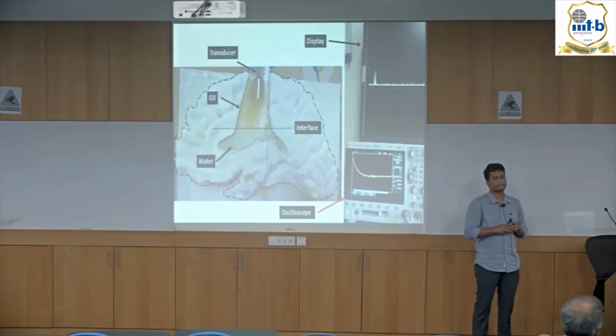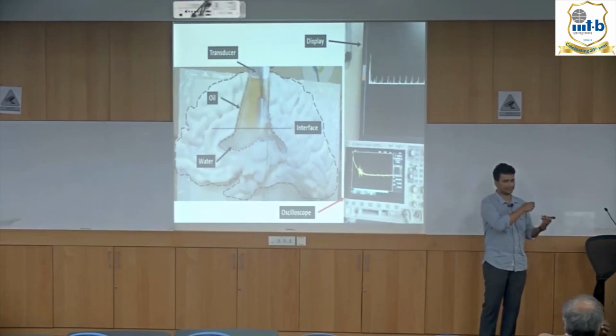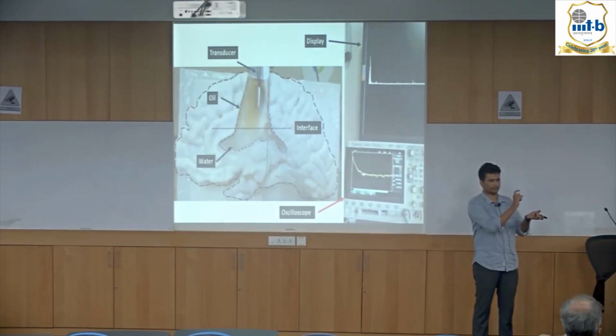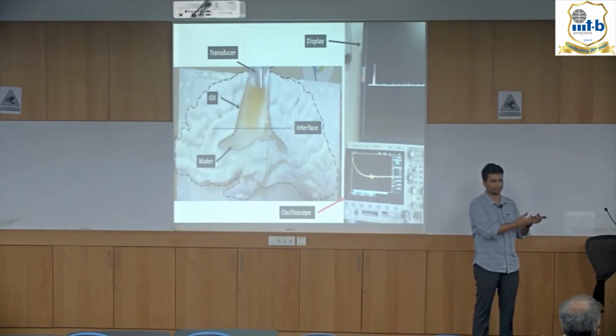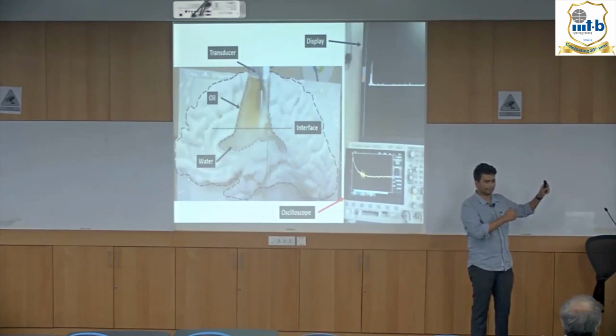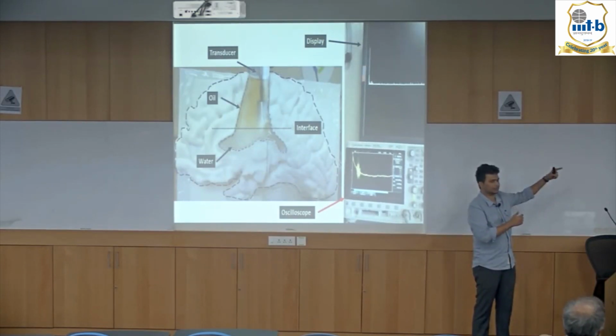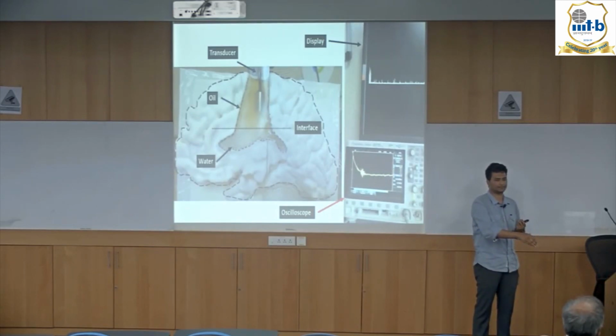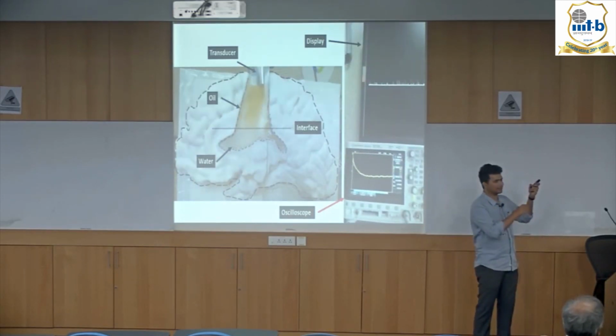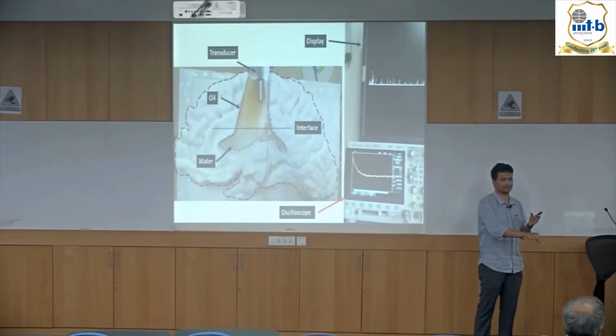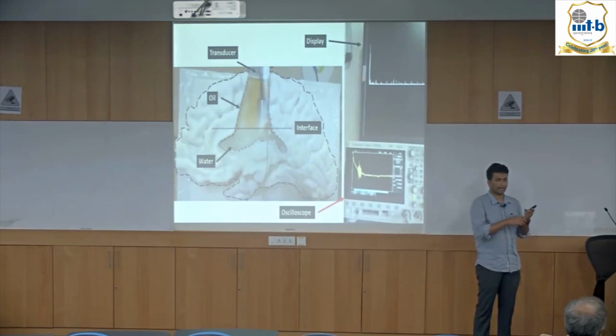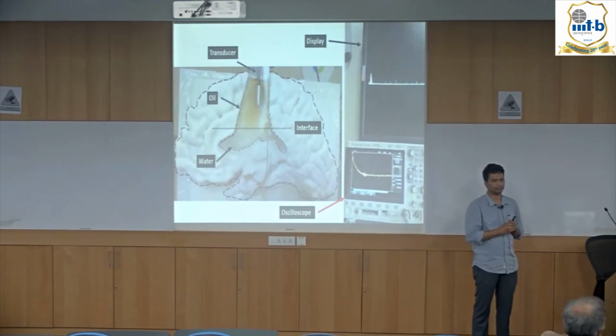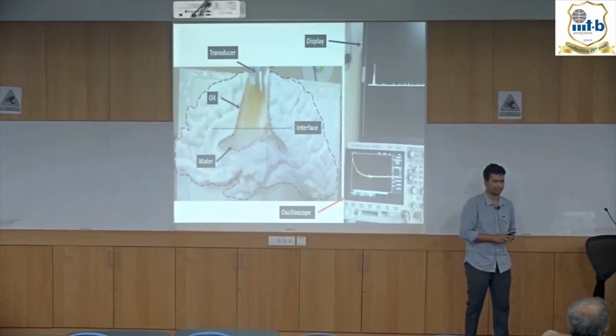If you change the fluid inside them, will you have to reprogram your array? No. The design of the transducer is itself a separate field, I mean the diameter and dimensions of the transducer. Right now we have chosen 8 mm because the interface between the oil and water is at around 3.5 to 4 centimeters, so the 8 mm diameter transducer will have a focus at that depth. The hardware doesn't change, but the transducer will probably change if we change the materials. Yes, that's the next part, which I'm going to explain.